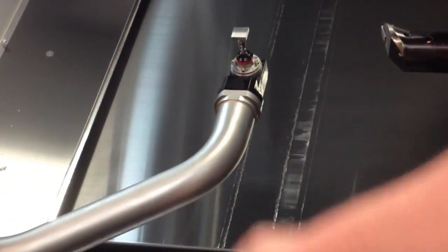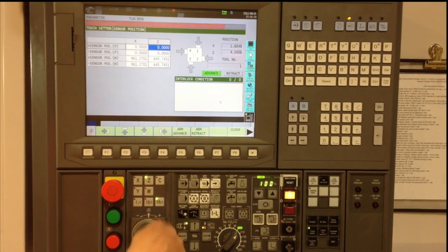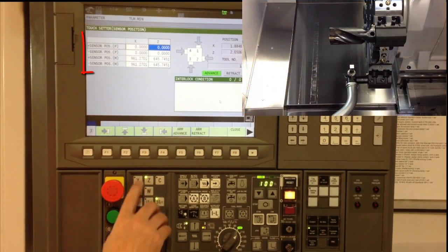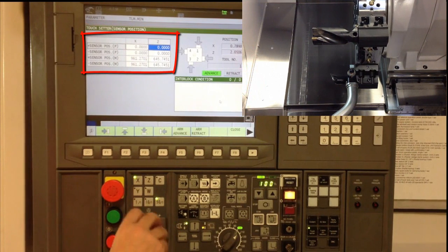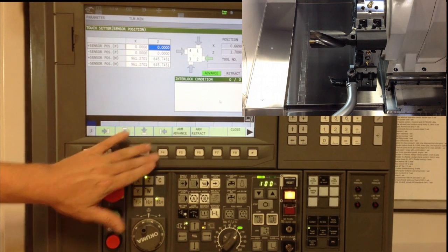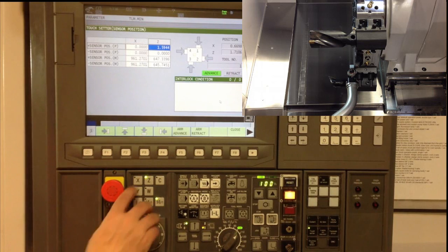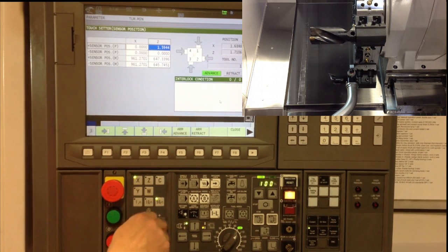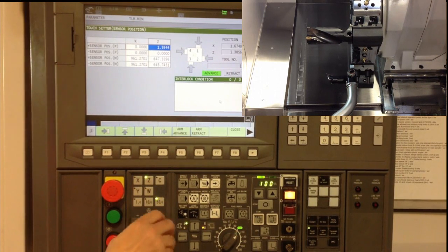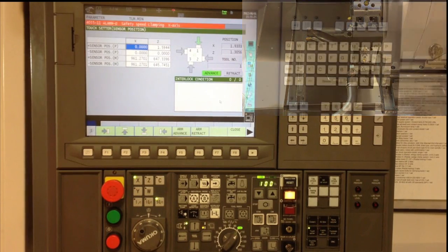Swing down the manual touch setter arm. The screen automatically changes to the Tool Offset page. Transition to the touch setter sensor position screen by pressing the parameter mode push button. Manually move the master tool off the right side of the touch setter probe cube. Press the left arrow key to start the calibration process in the X-axis. After completion, manually reposition the master tool over the top of the sensor cube and then press the down arrow key, completing the calibration in the Z-axis.